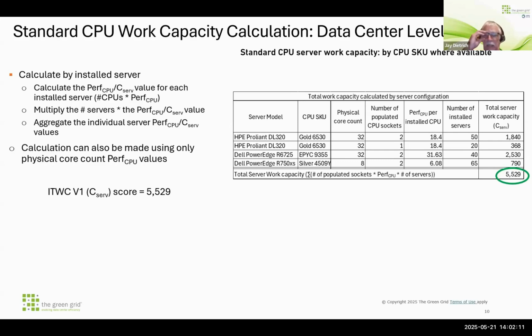There's a third method, which I didn't make a table for, but you could do the calculation just using the core count tables. That's a little less accurate than using the measurements, but we ran one test with a multi-generational set of CPUs, and the error between the CSERV value using all the measured per CPU values associated with the CPU SKUs was 4% below the CSERV value using the estimated values generated from the core count. So you've got pretty good alignment there, and any of these 3 methodologies will allow you to calculate the total work capacity of the standard CPU servers installed in the data center.